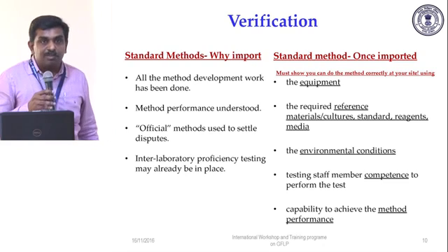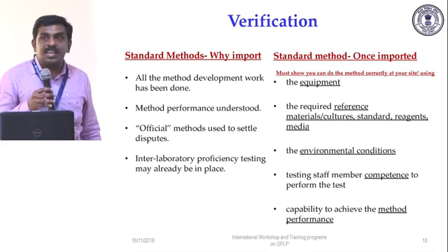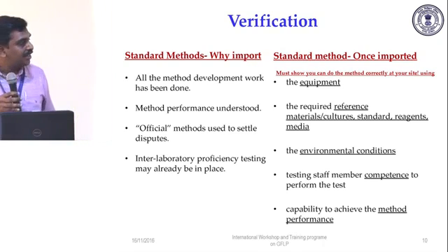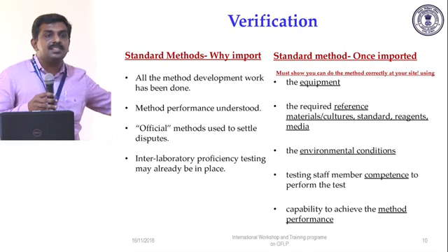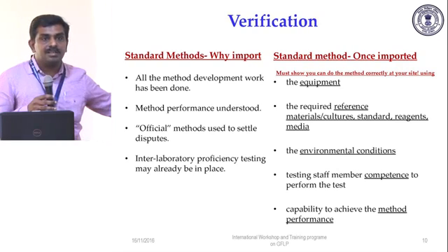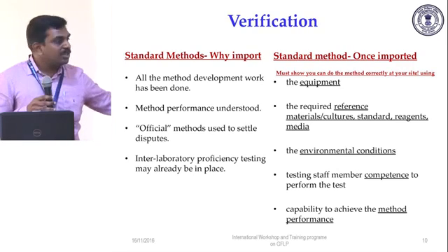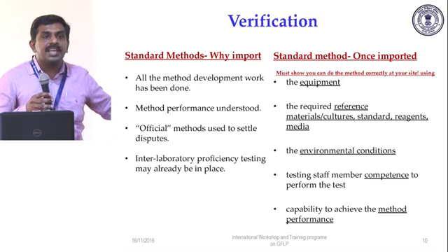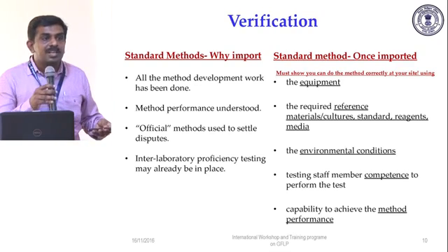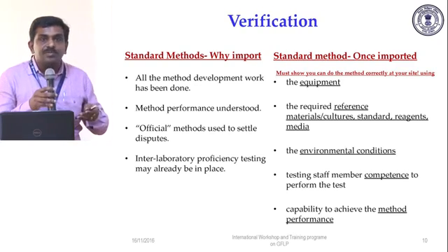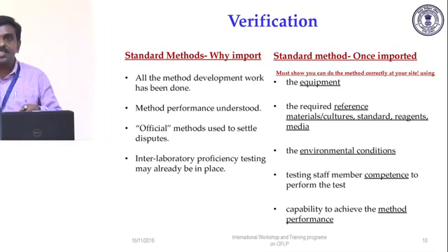By verifying your method, you also gain confidence that the analysts who are really working on the bench are competent, and have the capability to achieve the performance. That is listed in the definition also, because the method will have some performance. They would have told you the accuracy of this method, and the range of this method is from this to this. Many standard methods tell it. And the standard deviation has been this much, which means the precision.